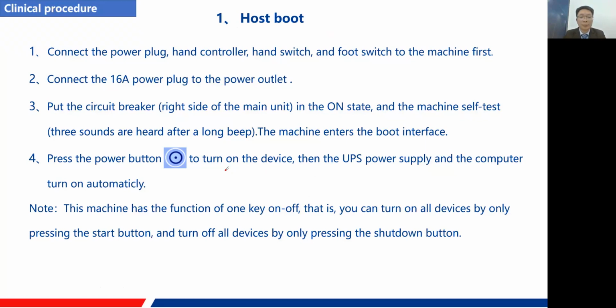Next is the host boot. I turn on the whole machine. Before testing the machine, we need to connect the power plug, the hand controller and the hand switch, foot switch to the machine first, and then connect the 16 ampere power plug to the power outlet. Here we also need to measure the power supply in the room. The power supply should be 220. And also the zero ground voltage should be less than 5 volts.